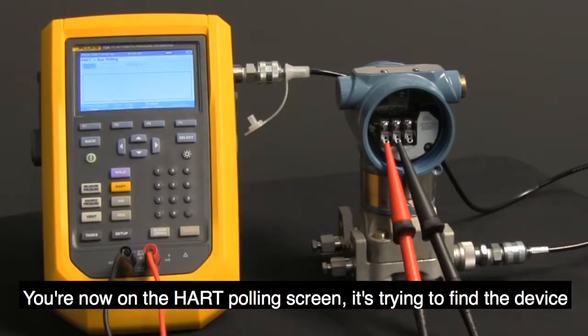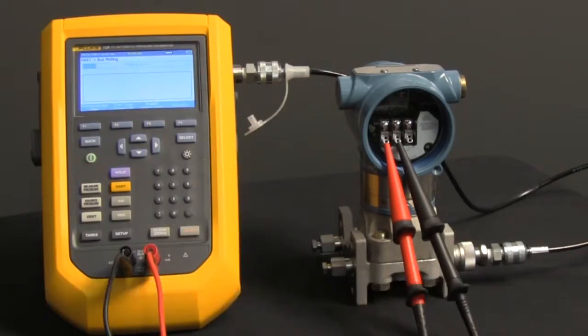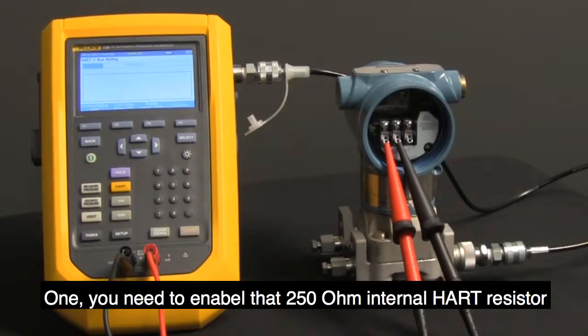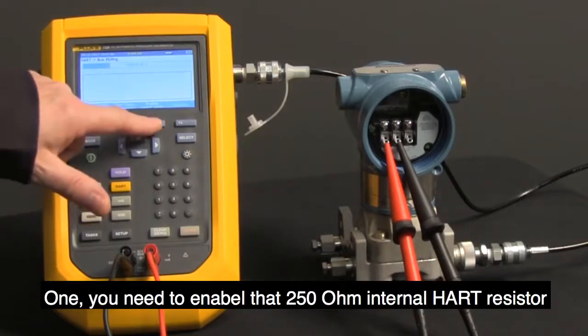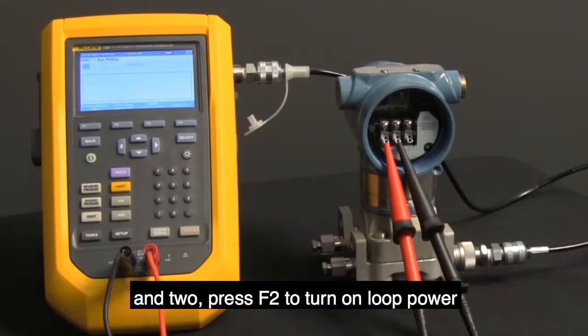You're now on the HART polling screen. It's trying to find the device. Two things you need to do: one, you need to enable that 250 ohm internal HART resistor, and two, press F2 to turn on loop power.